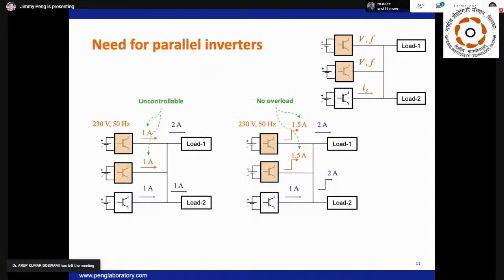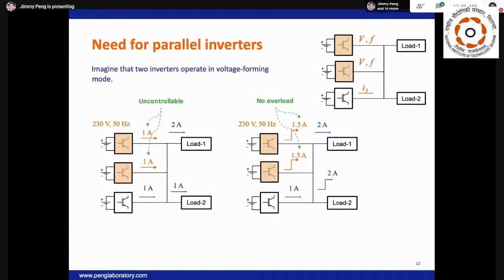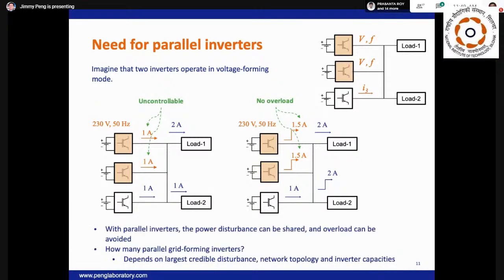Continuing with this example, but now we assign inverter 2 also as a grid-forming inverter. From our basic circuit theory, we can share the power disturbance using the 2 parallel inverters, which in return will be able to prevent the overloading scenario as witnessed in the previous slide. Again, the number of grid-forming inverters is an open question. The choice is dependent on the size and characteristic of the disturbance, network topology, and the rating of the inverters themselves. In practice, inverters can be adaptively set to grid-forming modes based on the needs of the microgrid.